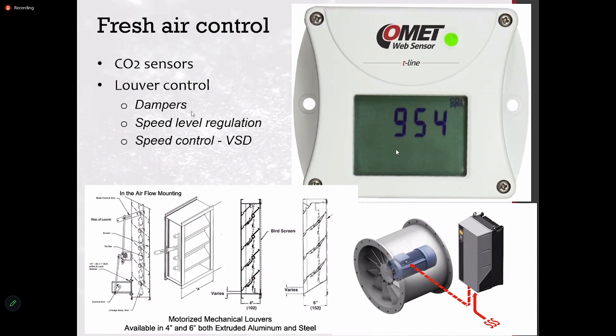Okay, so this could be even speed level regulated or VSD regulated. Because you will see, we will discuss, if the RPM comes down drastically, you are saving energy on the third order, because the power goes with the cube of the RPM, right? So it's on the third order, so you are cutting down a lot of energy. So if you can reduce the speed depending on the CO2 level, if it goes up very high, you can go to the full speed. Otherwise, you can have a minimum speed.